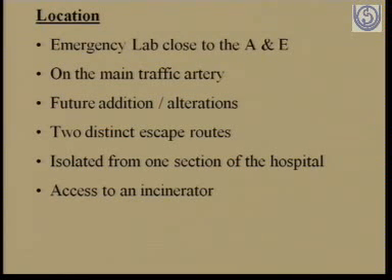It should be on the main traffic artery. Future additions and alterations: this is an area which is fast expanding, so you need to have space for future expansion. Two distinct escape routes from the safety point of view. It should be isolated from one section of the hospital, and access to an incinerator is required because you have to dispose of your biomedical waste.